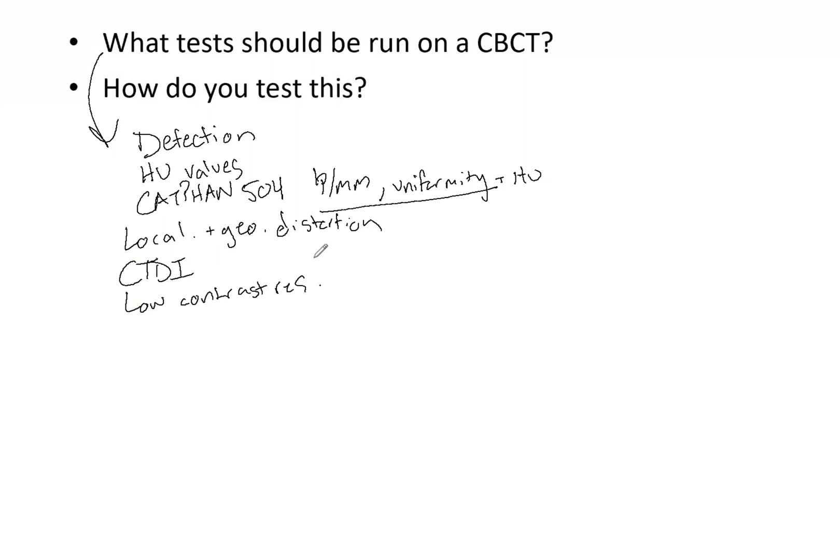For CTDI, you'll need your own system — a pencil ion chamber and specific phantoms to test for thorax and body. Know how to do that, and ideally you've done it yourself. For low contrast resolution, you can also use the CAT phantom, but there are dedicated phantoms like the Las Vegas phantom. Standard Imaging has a really good phantom that covers many of these tests. There are also dose analysis tools like Dose Lab or PIPS Pro — once you acquire a cone beam image of your phantom, you can import that image and run the tests on it.